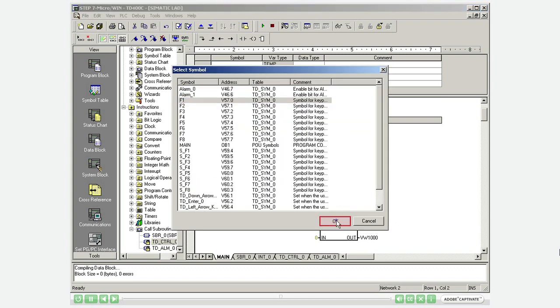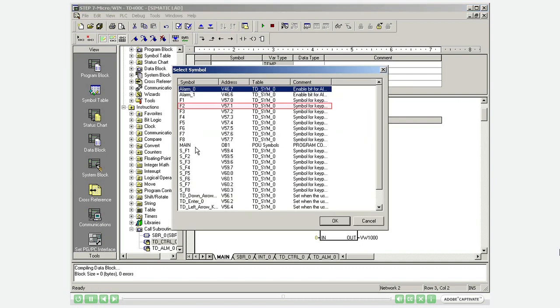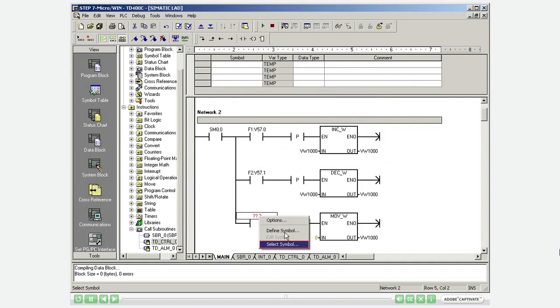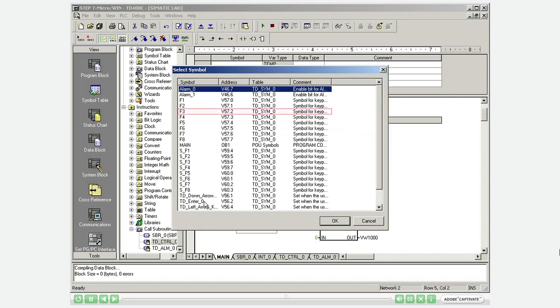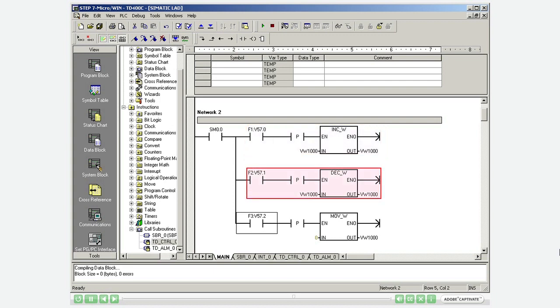You find the corresponding bit addresses by right clicking and selecting the symbol. The value of the chosen data address VW1000 will be incremented by pressing F1, decremented by pressing F2, and reset by pressing F3.